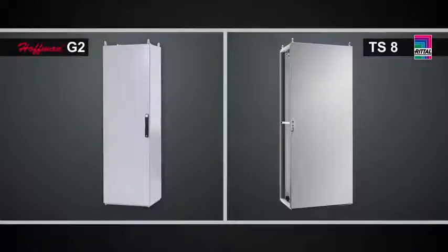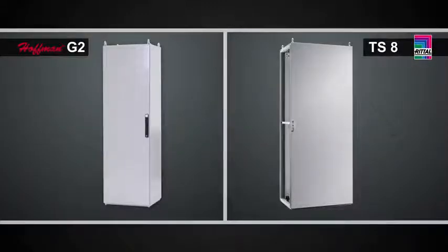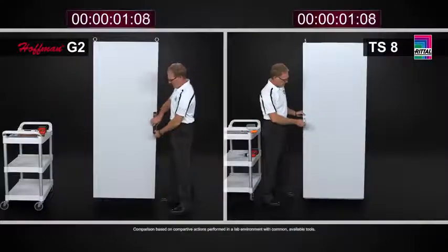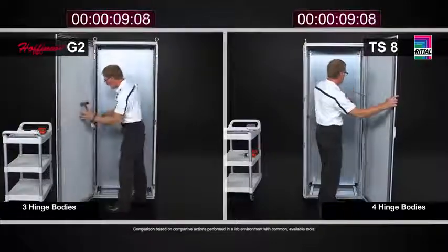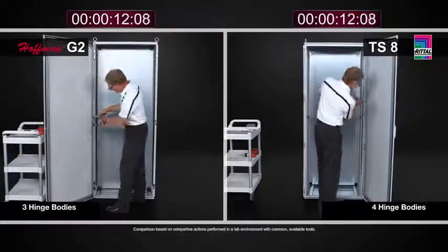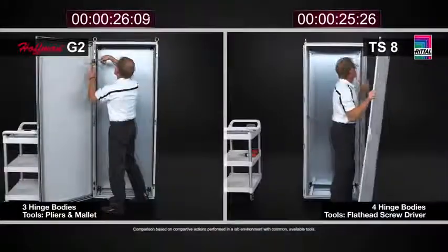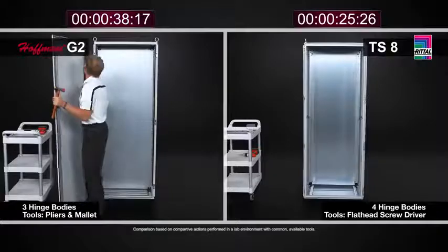The Rittal TS8 convention in Europe is a right-hand hinge door, and there are many reasons why somebody may want to remove the door — one, just to make it very easy to work in the cabinet, and another reason might be to put cutouts and holes in the door for controls like push buttons or HMIs. Taking off the door with the Rittal TS8 involves four hinge bodies. These hinge bodies have captive hinges — they are discrete hinge bodies, so there are four of them as standard on the right-hand side. By simply taking a flat blade screwdriver and popping the upper hinge pin up and the lower hinge pin down, you can do this with all four hinge bodies and very simply remove the door. This is a one-person task and it can be done very easily.